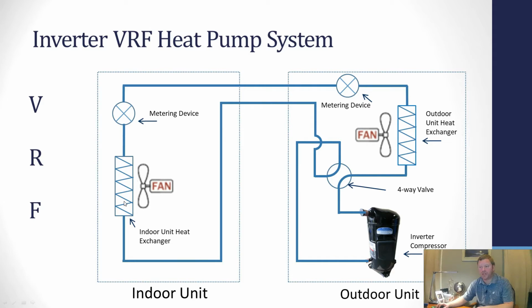So how much heat rejection takes place through that indoor unit heat exchanger, because when the refrigerant leaves that heat exchanger, it's supposed to be a liquid. And then once that refrigerant leaves the electronic expansion valve, it's supposed to have that pressure drop and be a low temperature, low pressure liquid. So how much of that heat transfer takes place can be directly controlled by that electronic expansion valve. And for reference, we're always trying to target around 9 to 10 degrees of subcooling. Again, we'll talk about this much more in detail at a later date, but that's something the mini splits can't do.